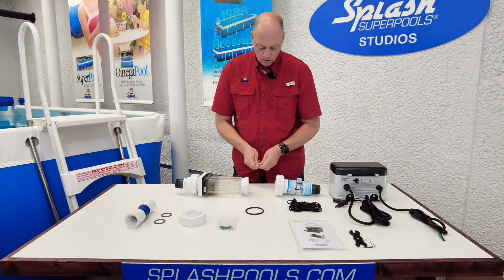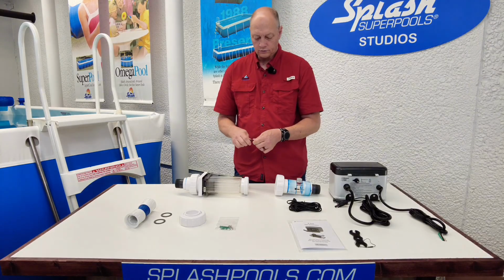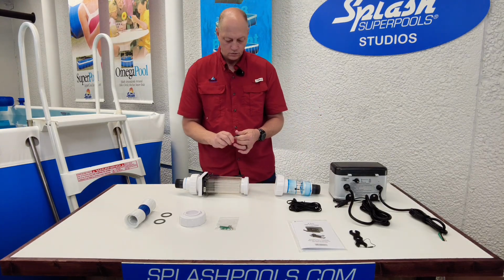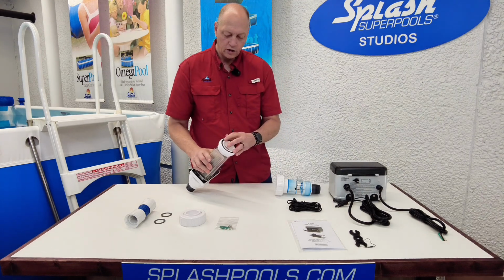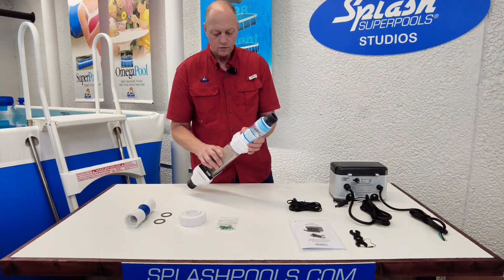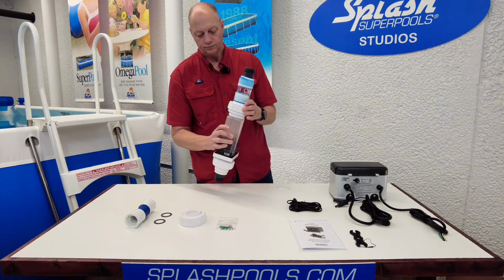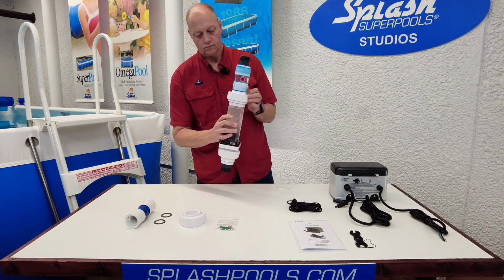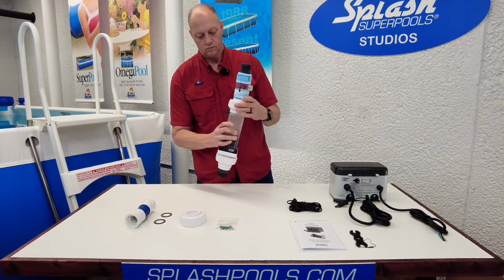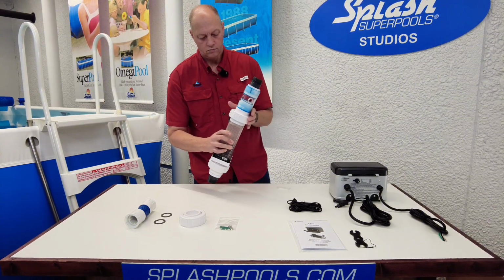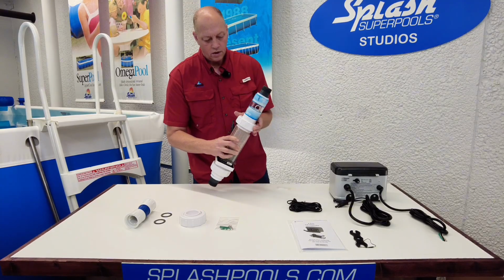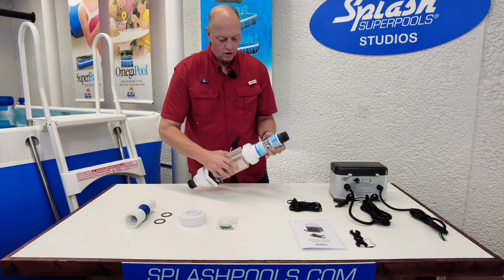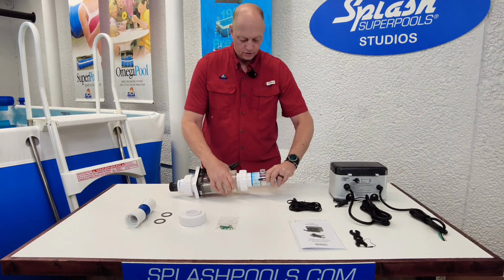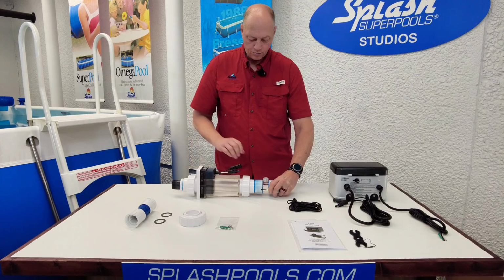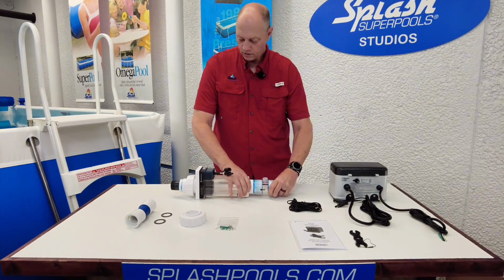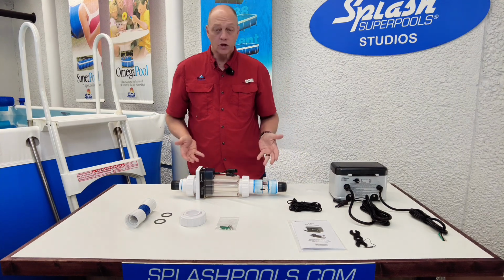I'm going to do the same thing with the other O-ring, placing it in the other end, in the groove. I'm going to put this end cap on, and before I get it snug, I'm going to make sure that this hole in the flow channel is pointing straight up. Then I'm going to tighten it down. So you should look like this.